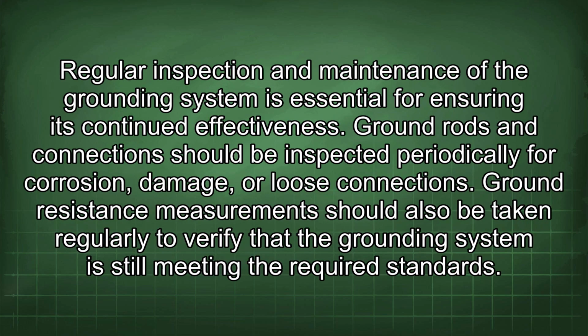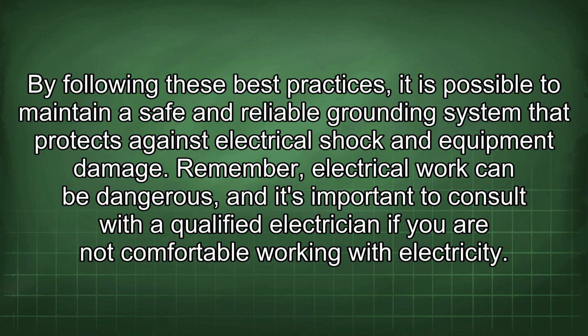Regular inspection and maintenance of the grounding system is essential for ensuring its continued effectiveness. Ground rods and connections should be inspected periodically for corrosion, damage, or loose connections. Ground resistance measurements should also be taken regularly to verify that the grounding system is still meeting the required standards. By following these best practices, it is possible to maintain a safe and reliable grounding system that protects against electrical shock and equipment damage. Remember, electrical work can be dangerous, and it's important to consult with a qualified electrician if you are not comfortable working with electricity.